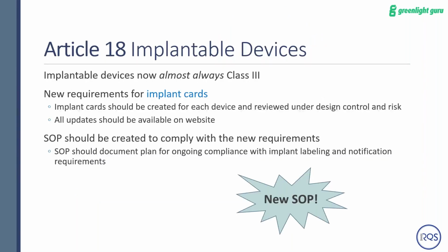All right, so for companies that are working with implantable devices, previously there were some changes, including MDR around classification. Now pretty much all implantables are class 3 at this point. With that, you'll have to have an implant card for each device that is implanted in a patient.